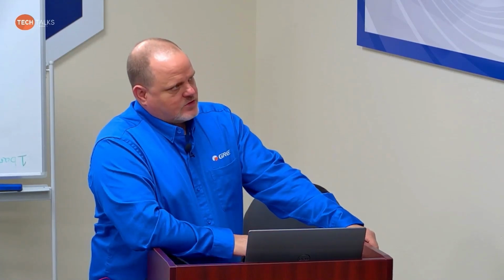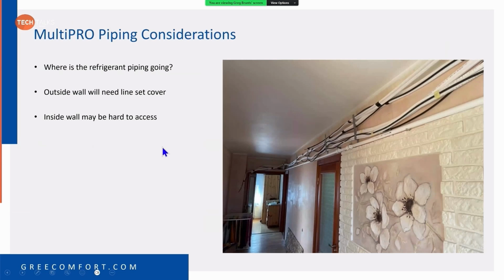If you're going to use a multiple Y system, more than one Y, we do require you go to selection software for that. Selection software is going to be able to show you properly how all those Y branches work out and get all the pipe sizes correct. And it'll also calculate your charge. So, moving on, again, make sure your refrigerant lines are going to be neat and proper and not looking like that, put it that way.